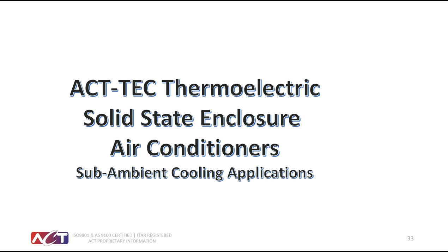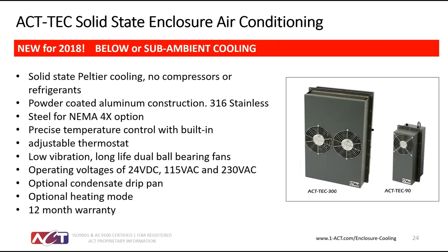Finally, in products, we'll talk about the thermoelectric or solid-state enclosure air conditioners. These are available in 90-watt formats or 300-watt formats, and the 300-watt is roughly about 1,000 BTUs of cooling. You can also get them in a NEMA 4X option, and they're very precise in their temperature control, and there's also no vapor compression cycle, so the reliability is very, very high.